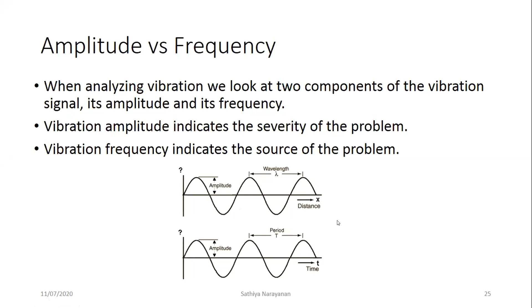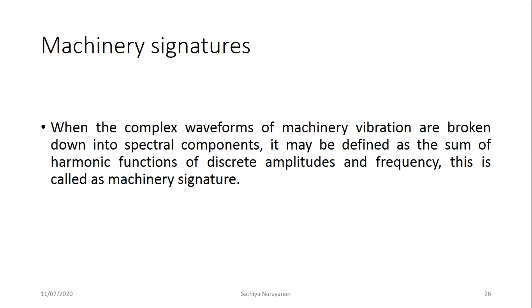As I told earlier, we have a System 1, which is a Bentley Nevada system. We have actually modified System 1 to such an extent that it checks the machinery vibration against predefined machine learning values, and gives an output on whether this particular equipment needs to be replaced or has a very severe problem. All these things are obtained from the harmonic functions of amplitude and frequency. We call this a machinery signature.